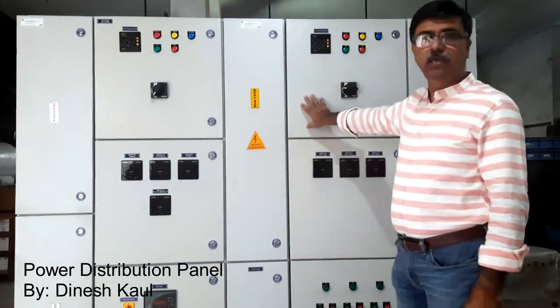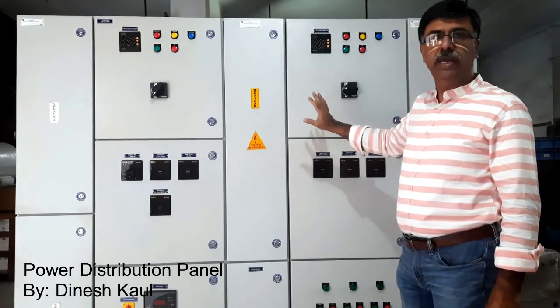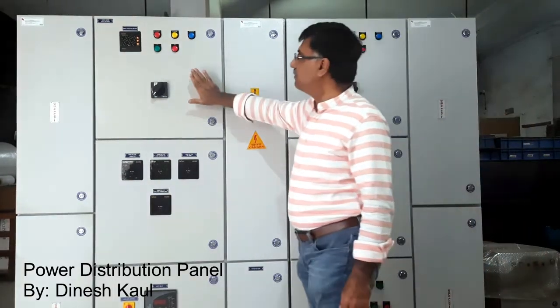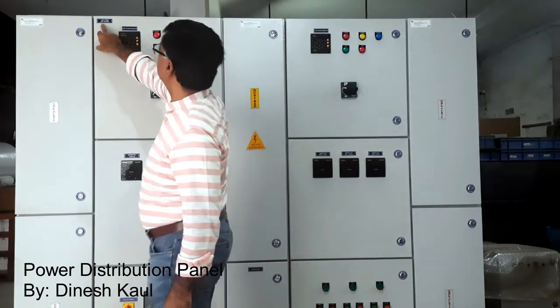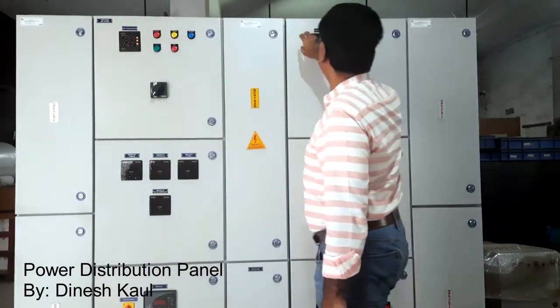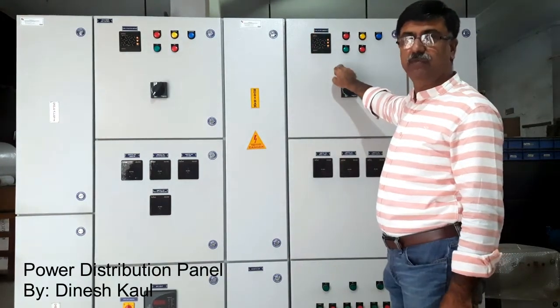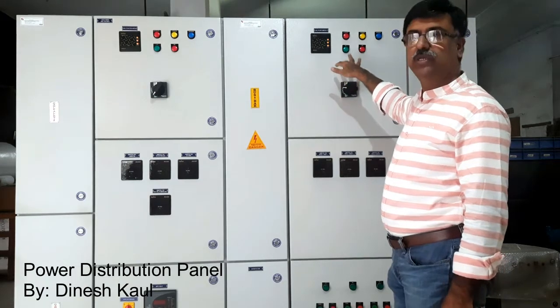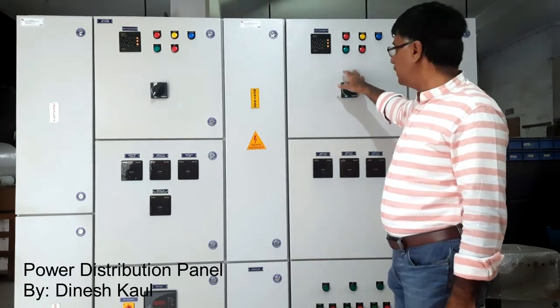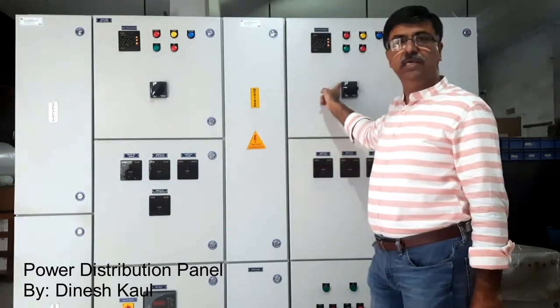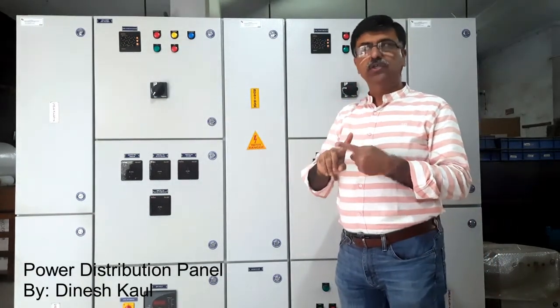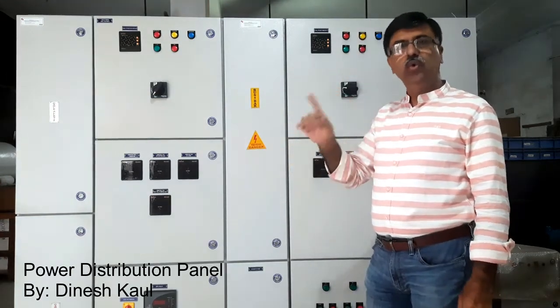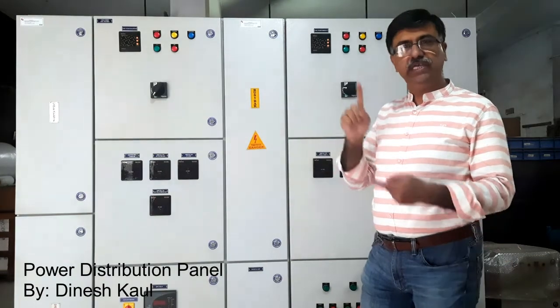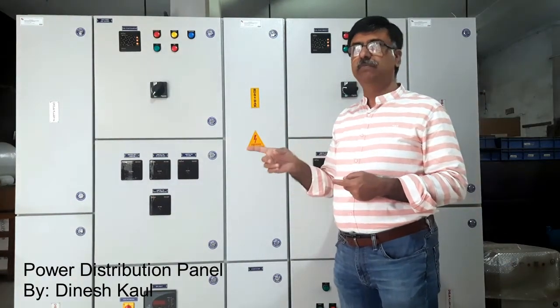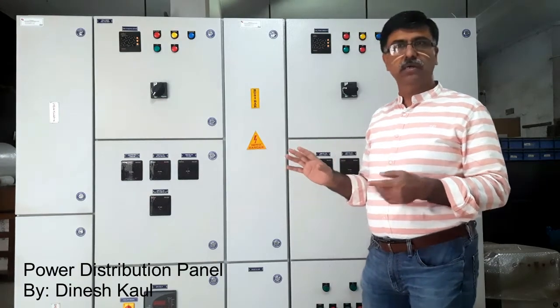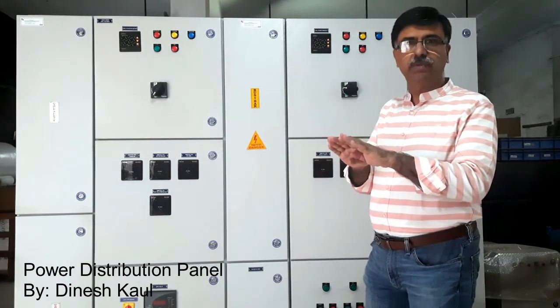So this is a typical power distribution main incoming panel that you will have. For example, it has a main incoming of 400 ampere MCCB as a grid incomer. Then it has another incomer, which is the DG incomer, which may be for 200 kVA, so 320 ampere MCCB. And these are both mechanically and electrically interlocked, so that at any given point of time only one incomer will be active. So either the DG will be supplying or the grid will be supplying. There will be no other short circuit. You cannot have both the supplies supplying at the same time.